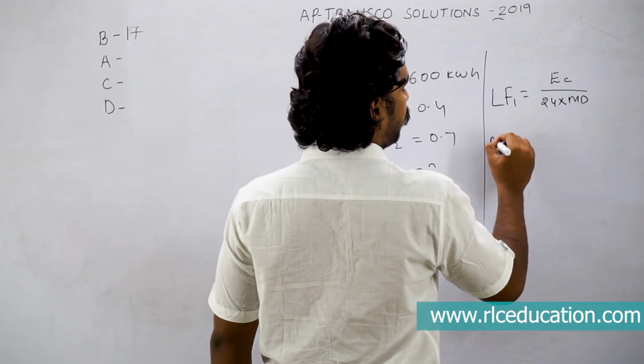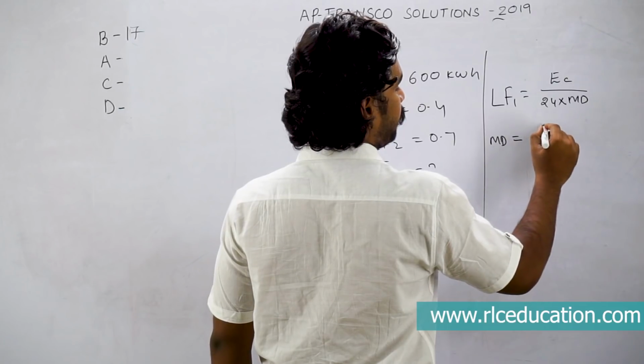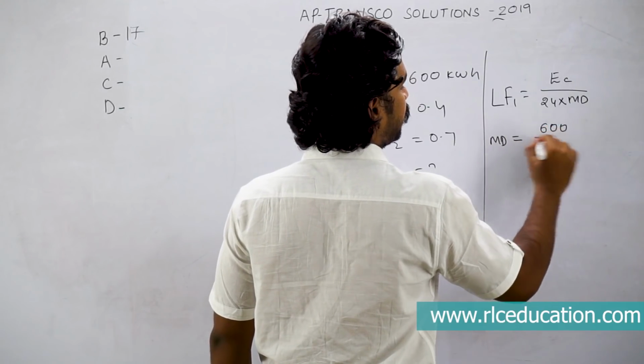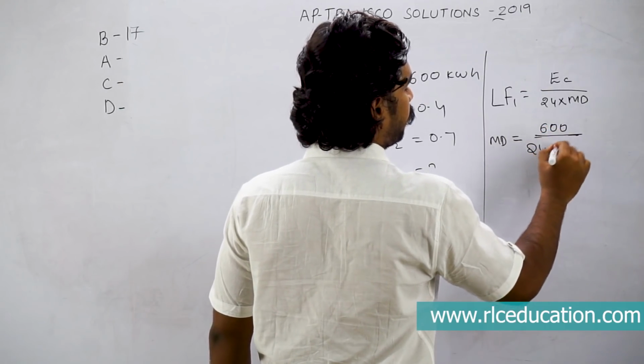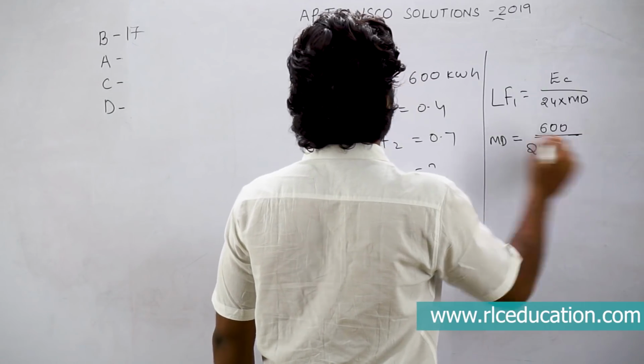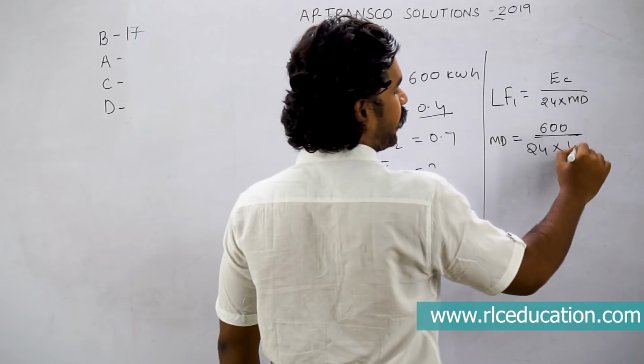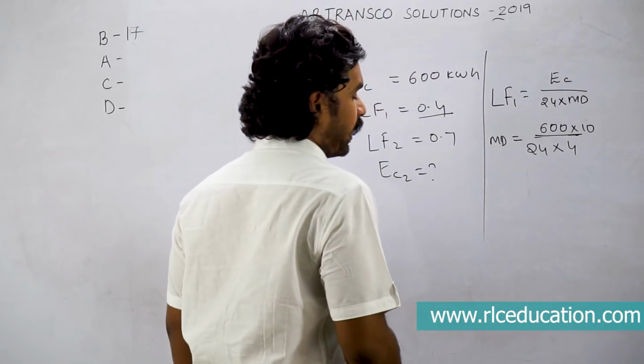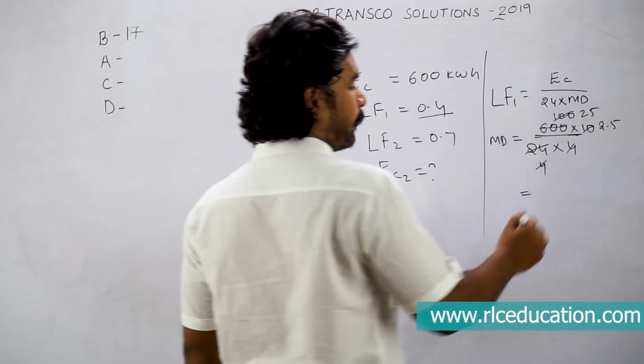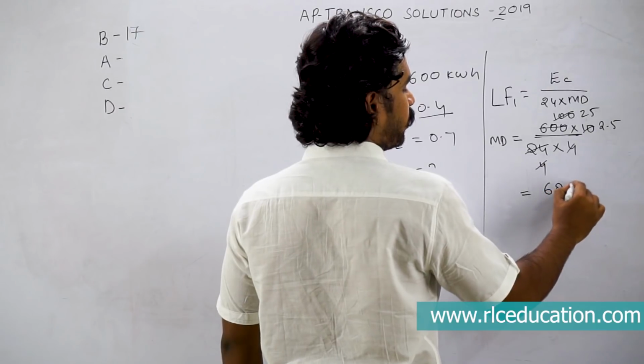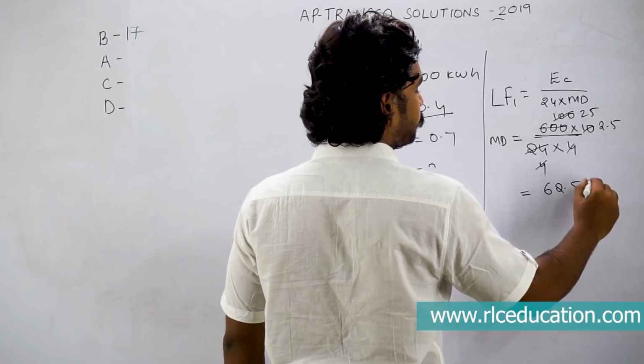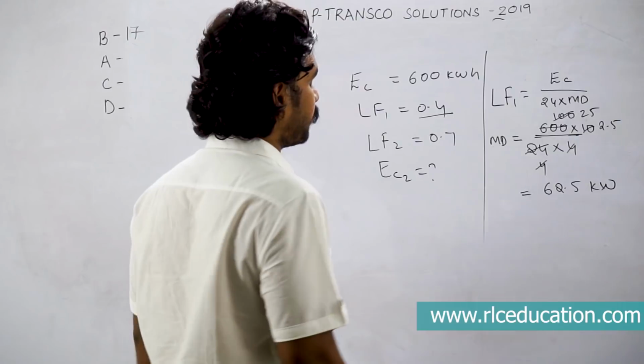From this you can find the maximum demand. Maximum demand equals energy consumed in a day, that is 600 kilowatt hour, divided by 24 into load factor, which is initially 0.4, or 4 by 10. Upon solving this, maximum demand comes out to be 62.5 kilowatts for this consumer.